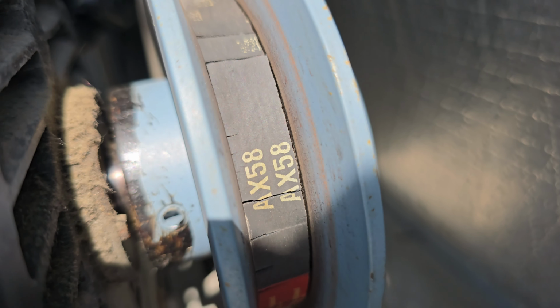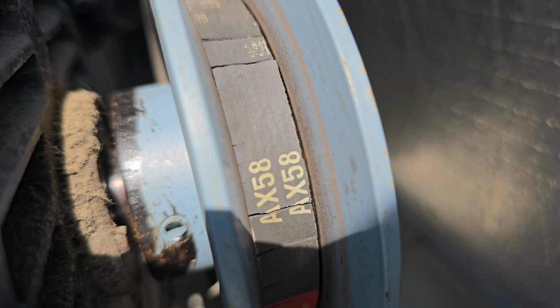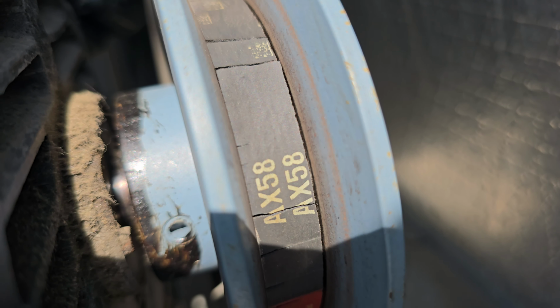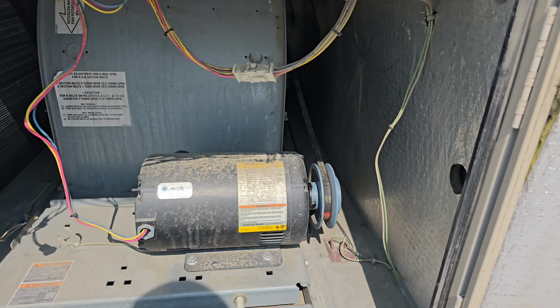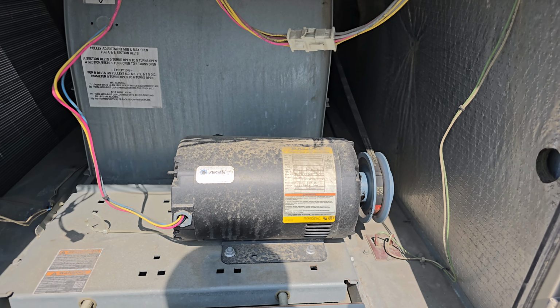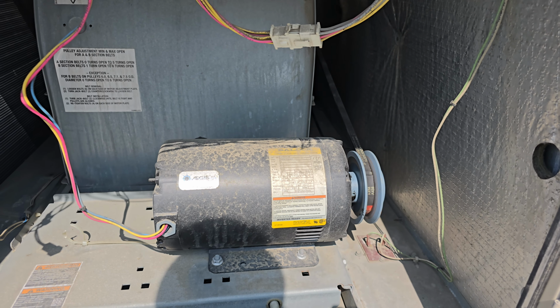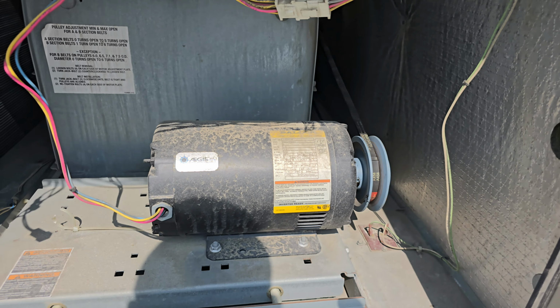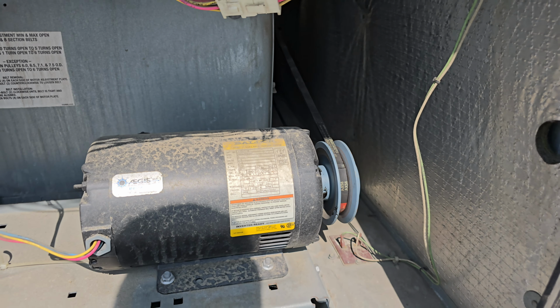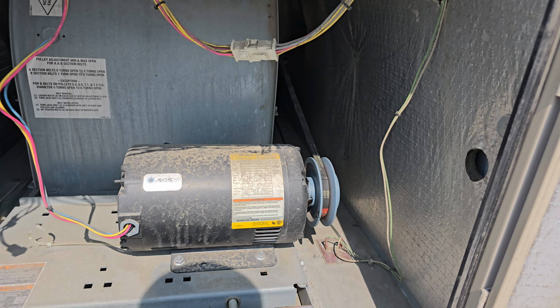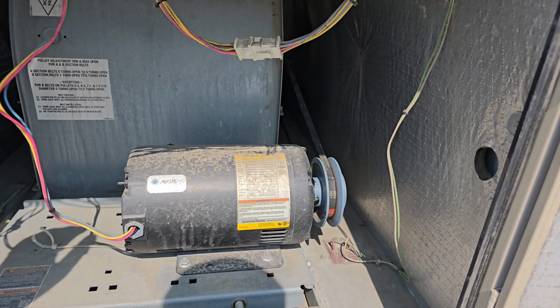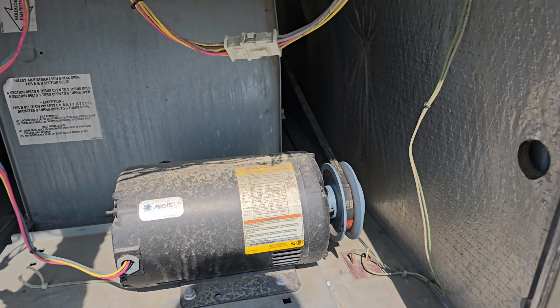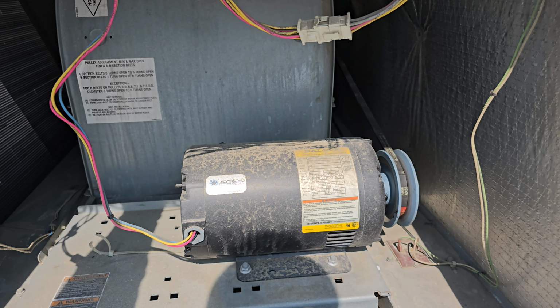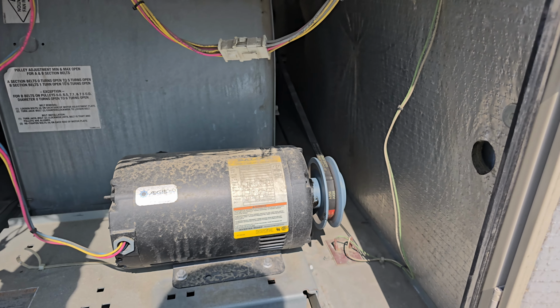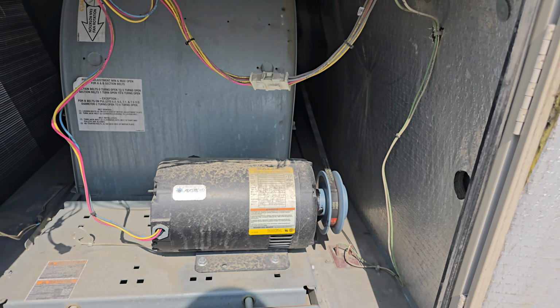What's the size of my belt? It's an AX58, so this is bad. When the belt is bad, it's not able to pull enough CFM, which can reduce the amps or efficiency of the motor, and you might not get enough airflow. So I'm going to change this belt.